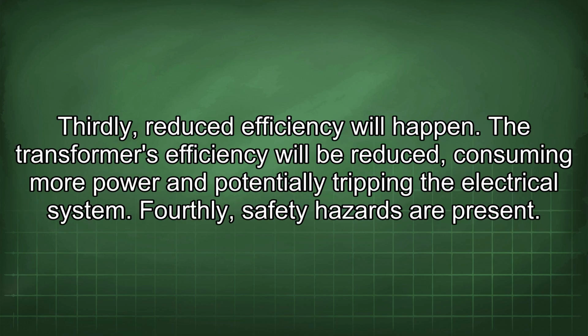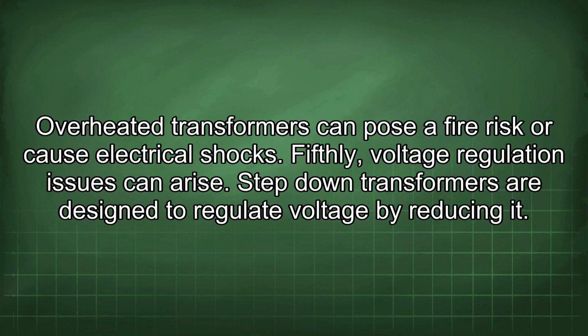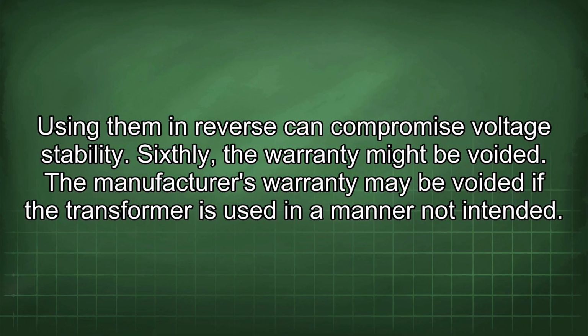Thirdly, reduced efficiency will happen. The transformer's efficiency will be reduced, consuming more power and potentially tripping the electrical system. Fourthly, safety hazards are present. Overheated transformers can pose a fire risk or cause electrical shocks. Fifthly, voltage regulation issues can arise. Step-down transformers are designed to regulate voltage by reducing it. Using them in reverse can compromise voltage stability.